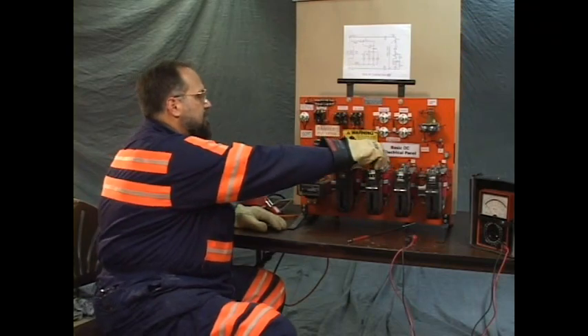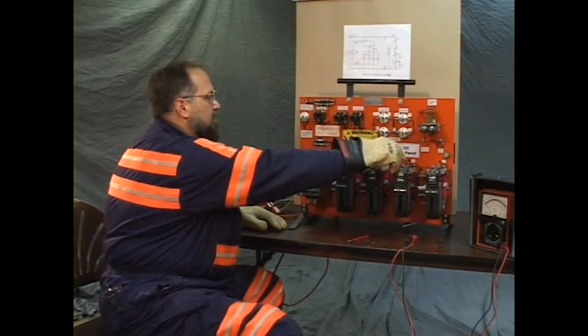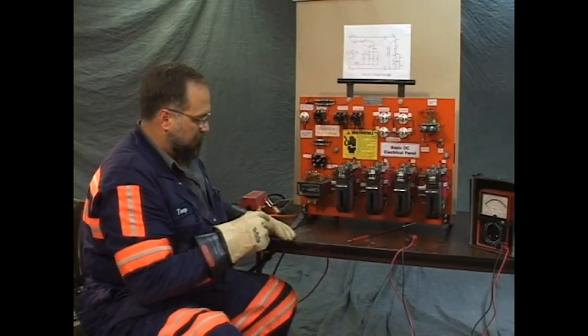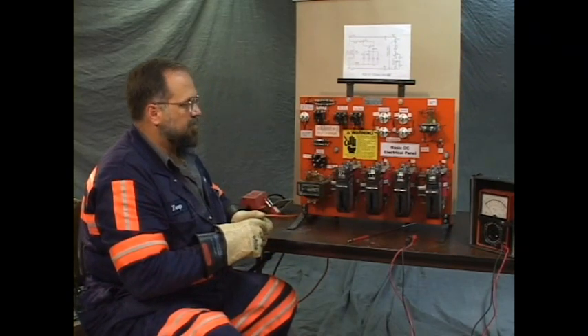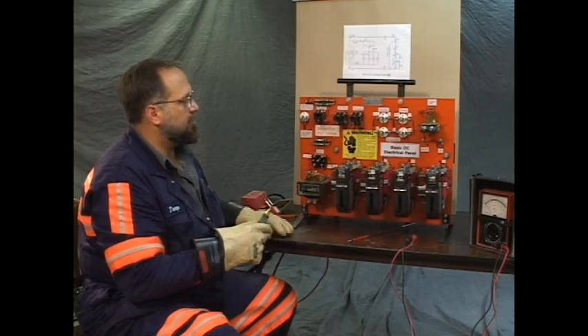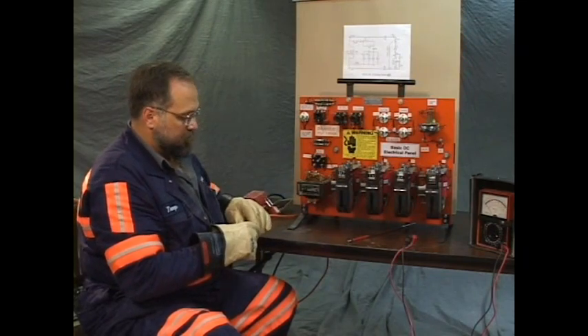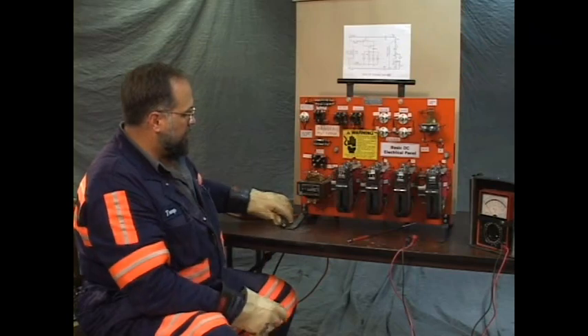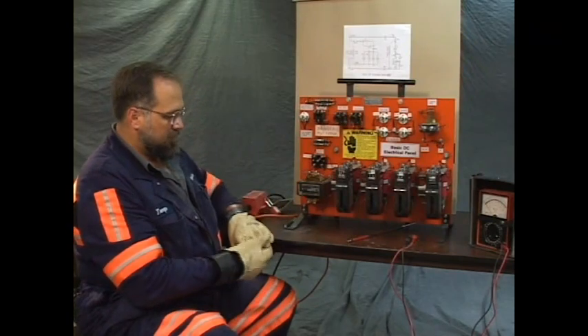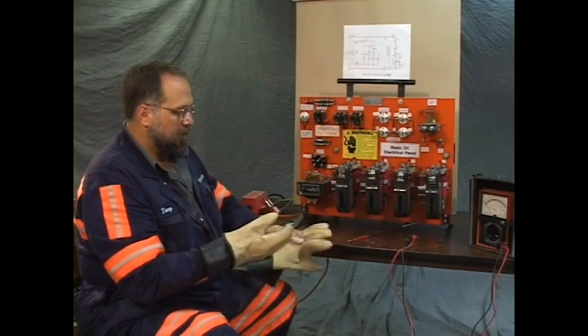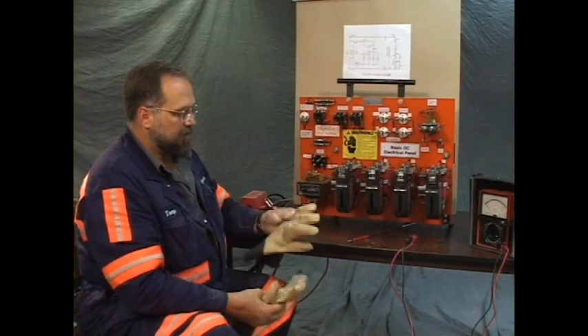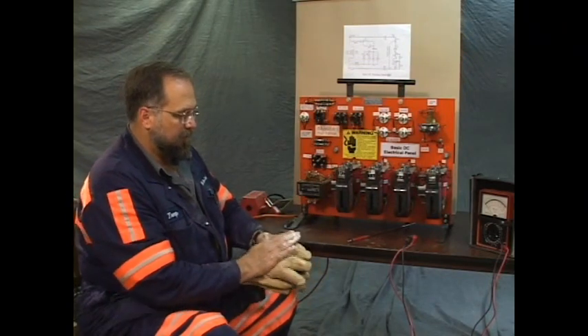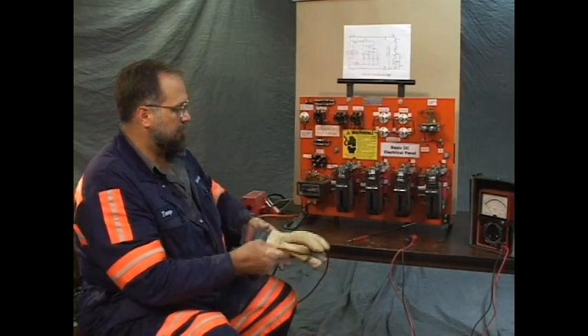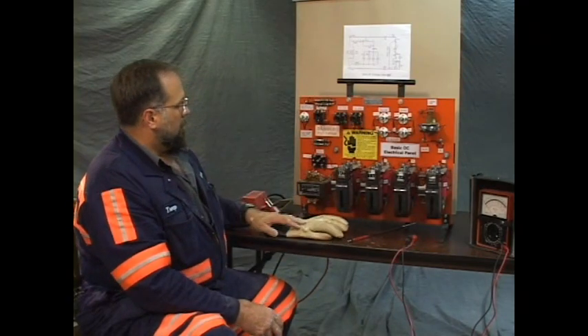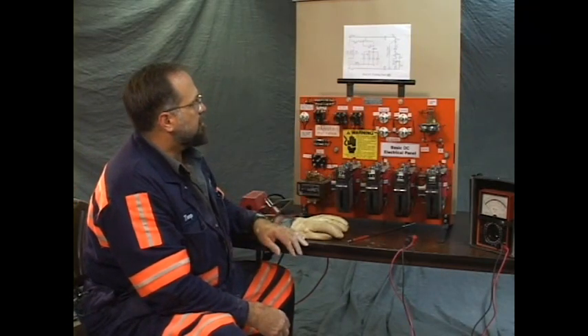Now, it's not recognized as a DC tester because DC doesn't have the necessary relative motion to operate this. But with this panel, we're powered with an AC power supply going to a rectifier, and it will detect this particular kind of DC. It's a chopped DC, and then it will detect it. We've established that the source power is off and the panel is safe to test.